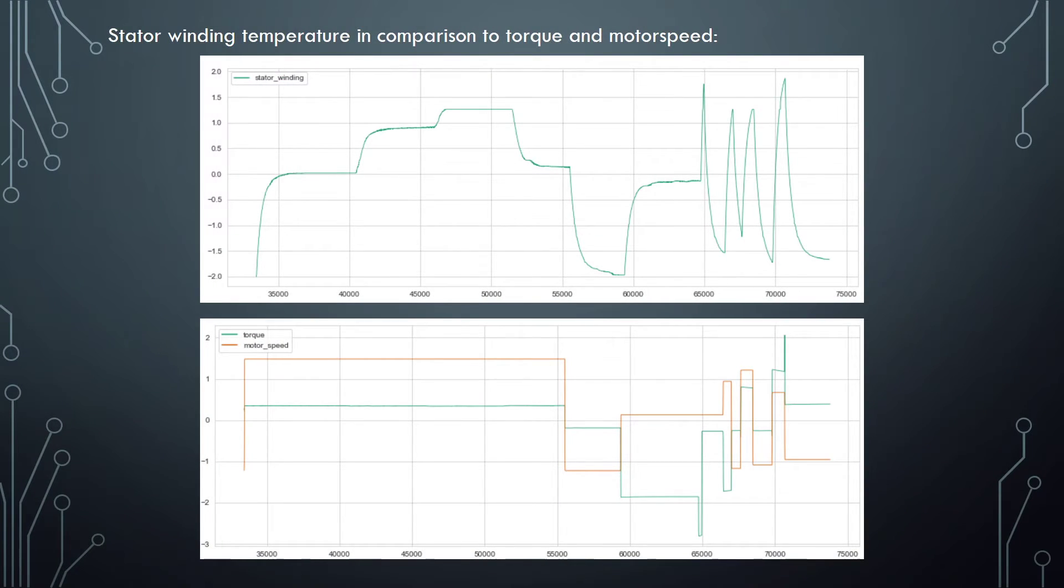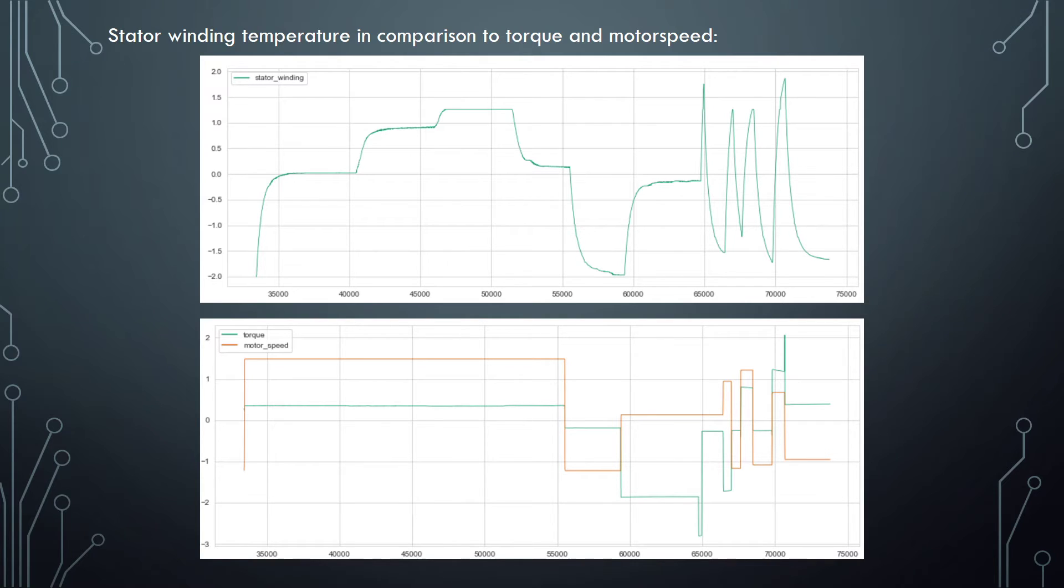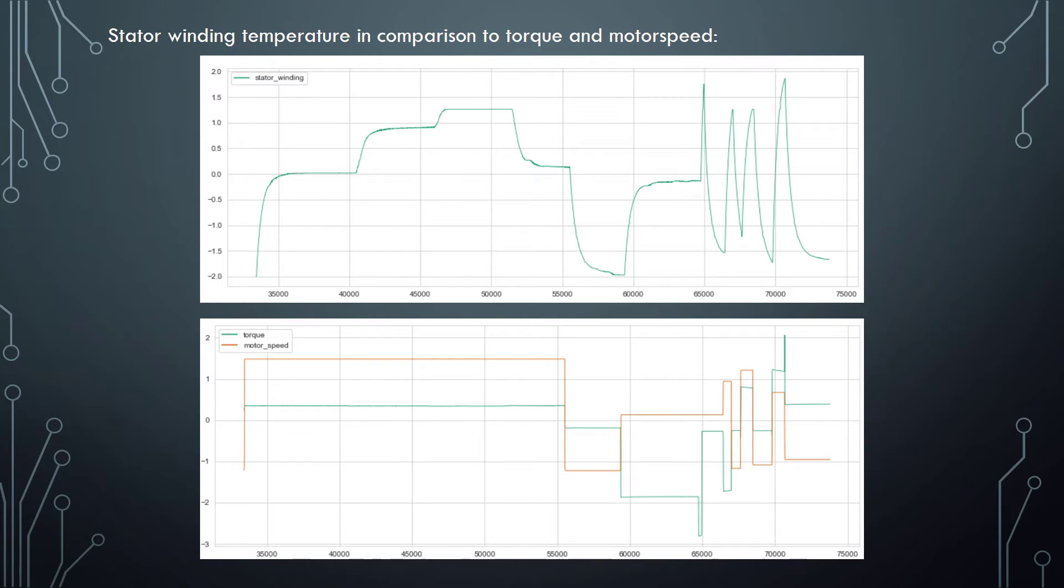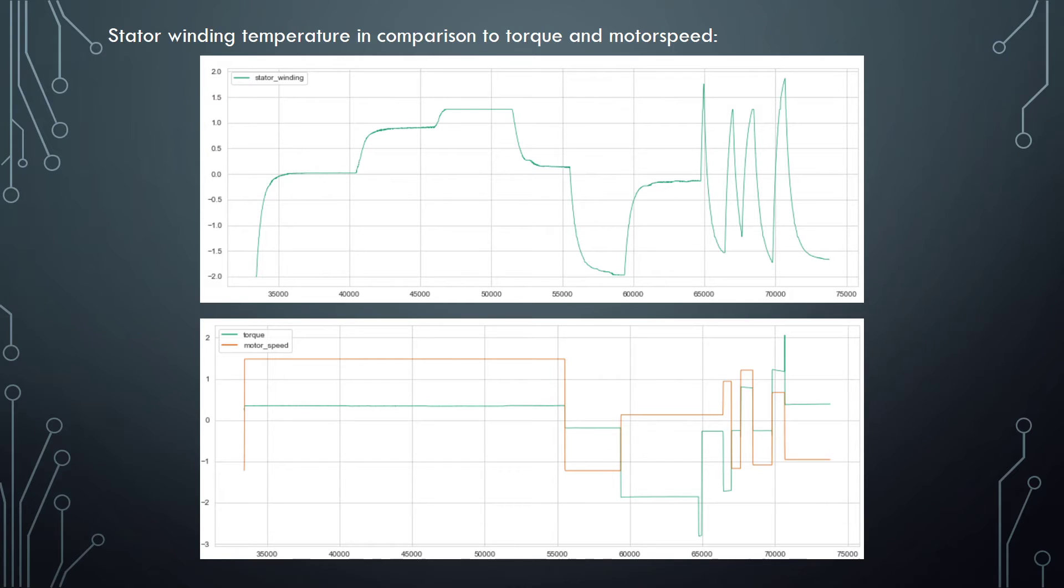On this slide we can see plots of stator winding temperature in comparison to torque and motor speed for test run 6. In the second part of the above test run there seems to be a relation between the stator temperature, torque and motor speed. When the torque and/or motor speed is increased, the temperature rises and vice versa. However, looking at the first part of the plot, this is not always the case. Even with constant torque and motor speed the stator winding temperature shows several sudden changes in temperature. In other words, there seem to be one or more other variables which have an impact on the stator temperature.